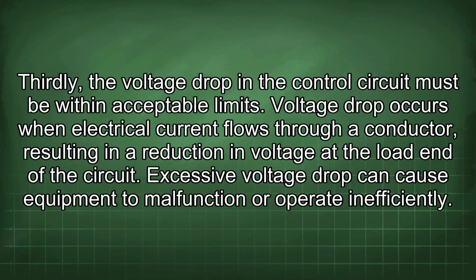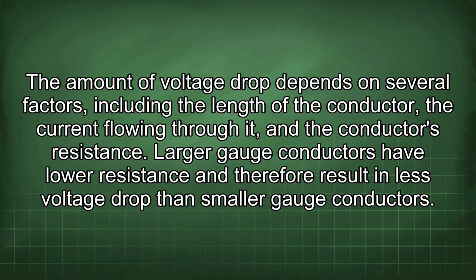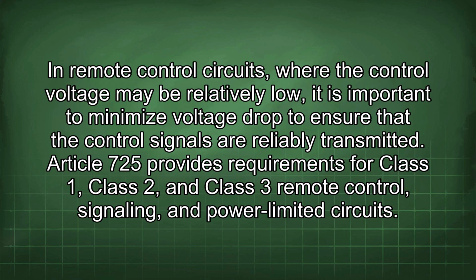Thirdly, the voltage drop in the control circuit must be within acceptable limits. Voltage drop occurs when electrical current flows through a conductor, resulting in a reduction in voltage at the load end of the circuit. Excessive voltage drop can cause equipment to malfunction or operate inefficiently. The amount of voltage drop depends on several factors, including the length of the conductor, the current flowing through it, and the conductor's resistance. Larger gauge conductors have lower resistance and therefore result in less voltage drop than smaller gauge conductors. In remote control circuits, where the control voltage may be relatively lower, it is important to minimize voltage drop to ensure that the control signals are reliably transmitted.